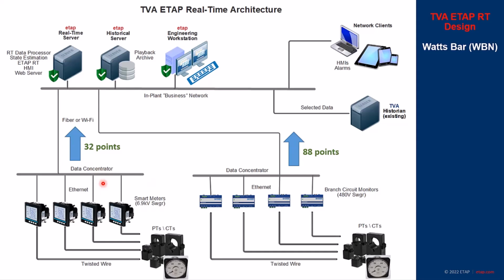And what's really interesting about an ETAP RT system like this, and the real strength of it, is that people say, well, Mark, why wouldn't we just hook up smart meters, and why do we need ETAP real-time? Well, because we're getting about 32 points out of the 6.9 kV and about 88 points out of the 480. But by going up to the ETAP real-time server and using the state estimation, in other words, using our ETAP model, we can then realize about 15,000 points that are available for playback or real-time viewing out to the network clients. And also we save selected data to our TVA historian. So that's the real power, going from just a little over 100 points to 15,000 points.